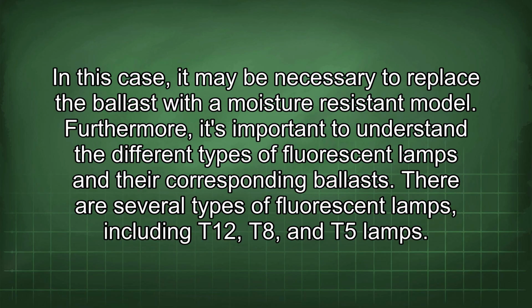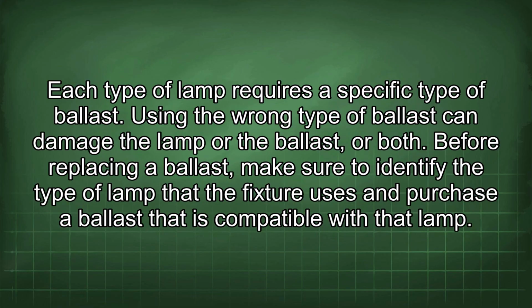Furthermore, it's important to understand the different types of fluorescent lamps and their corresponding ballasts. There are several types of fluorescent lamps, including T12, T8, and T5 lamps. Each type of lamp requires a specific type of ballast. Using the wrong type of ballast can damage the lamp or the ballast, or both.